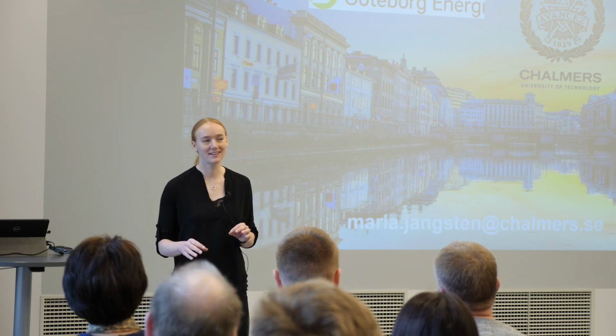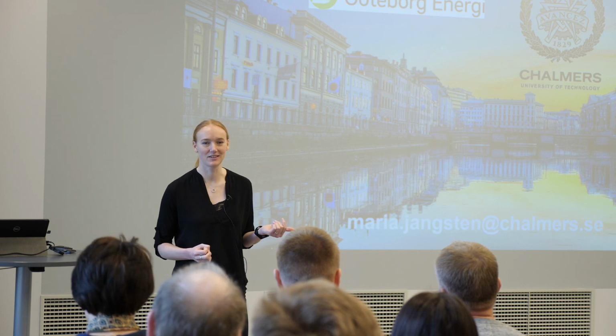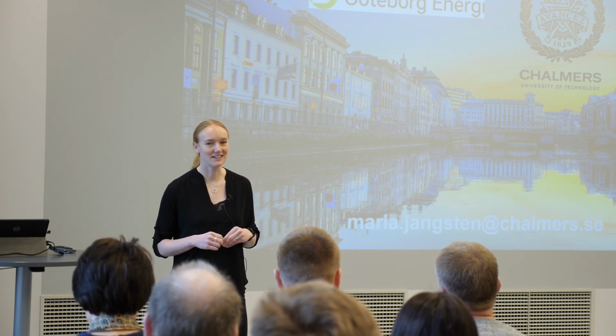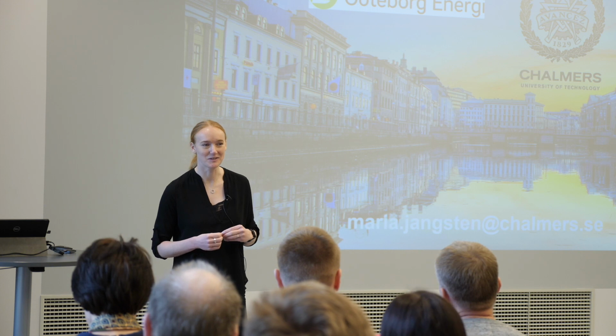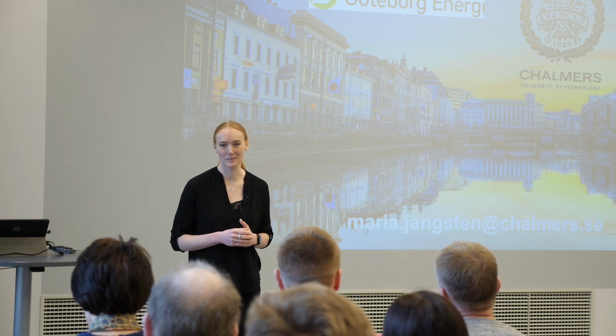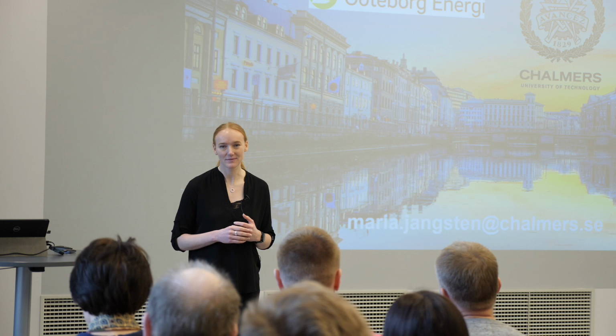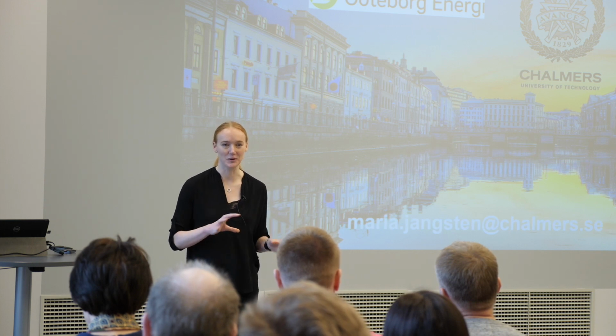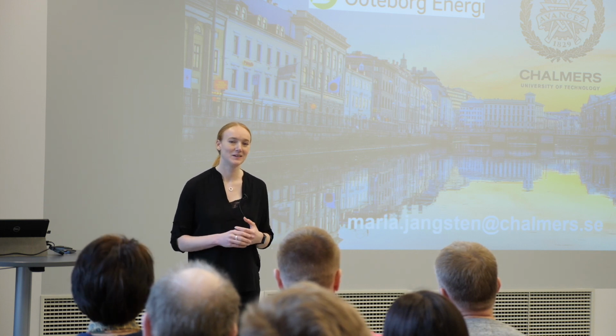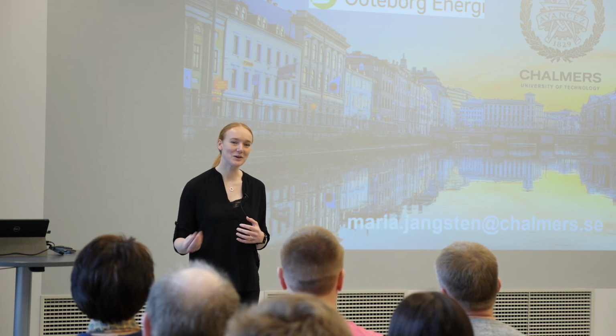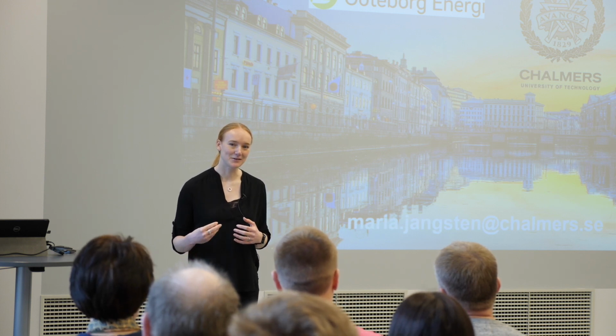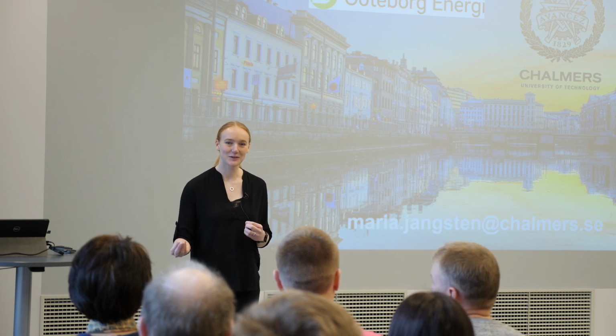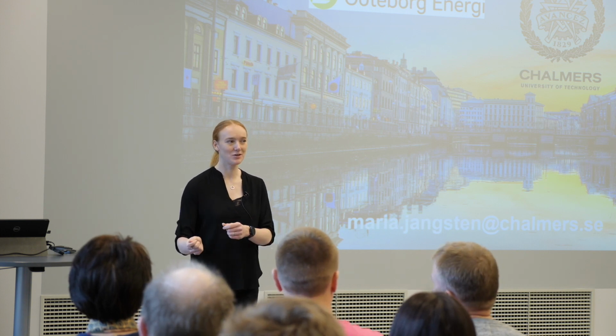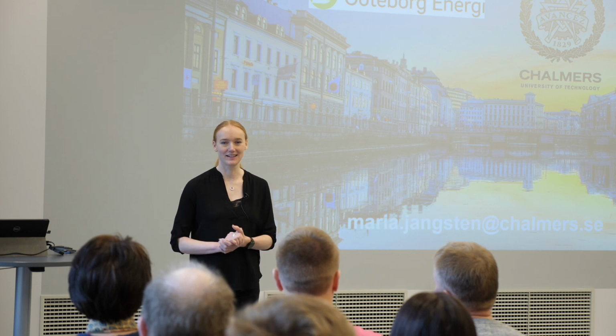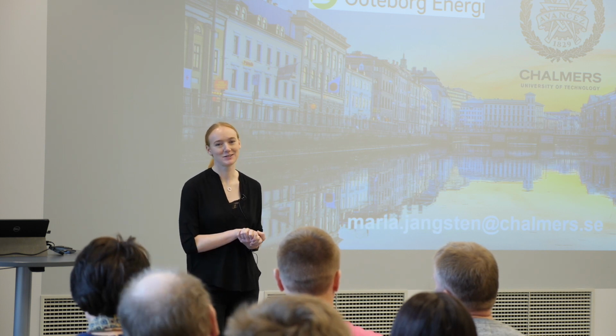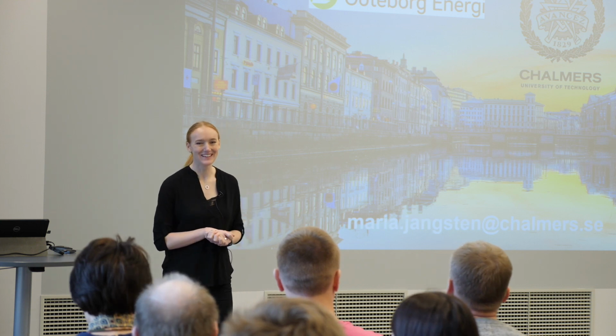But in the summer, the district cooling provider in Gothenburg, Göteborg Energy, is not interested in raising the supply temperatures, actually rather the opposite, so they can meet the maximum demand. But I think it's definitely interesting in the transition parts of the year, spring and fall. But it requires communication with the customer, and they haven't really had that sort of communication. They're like, okay, we're gonna give you 6 degrees all time of the year, and that's it. But they should start that.